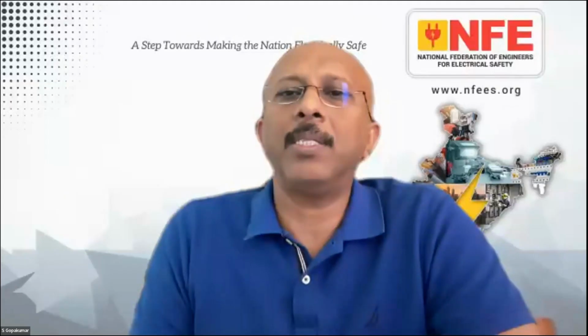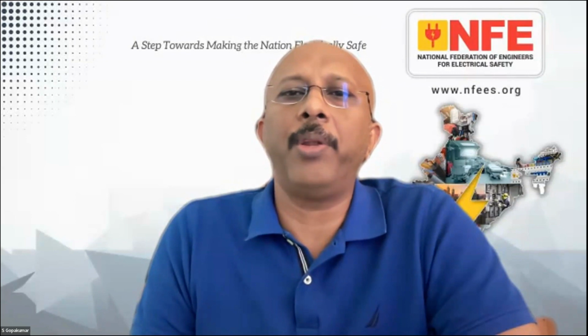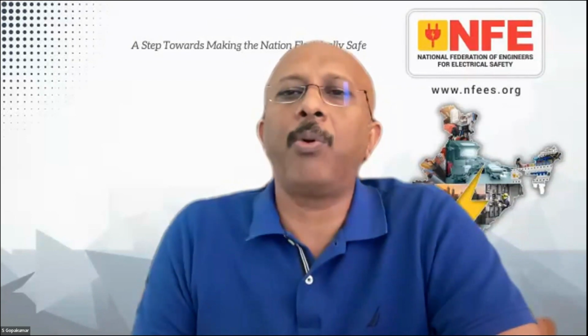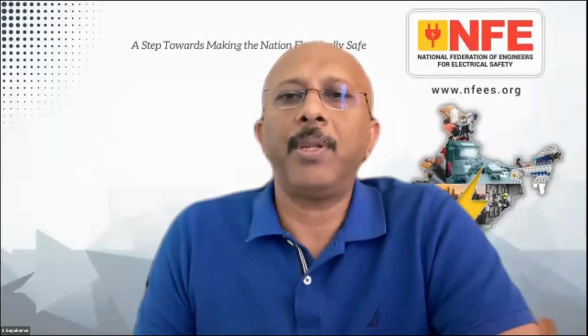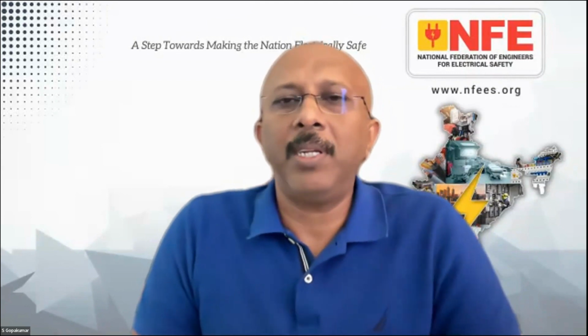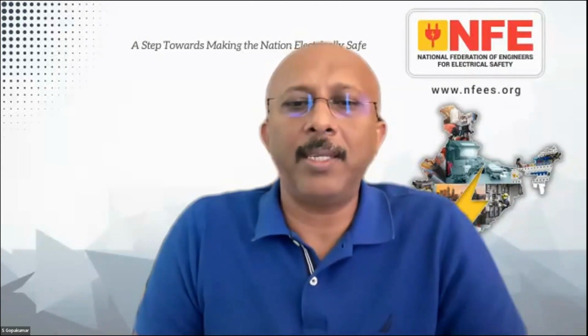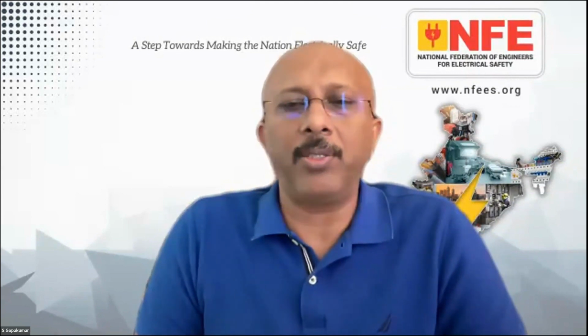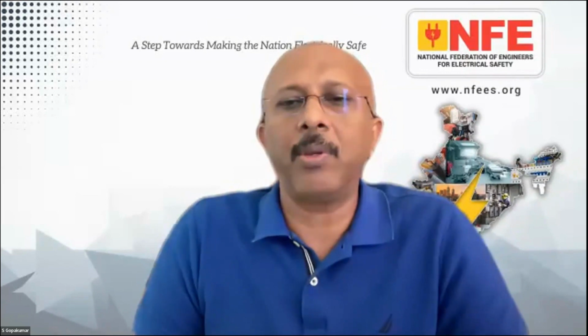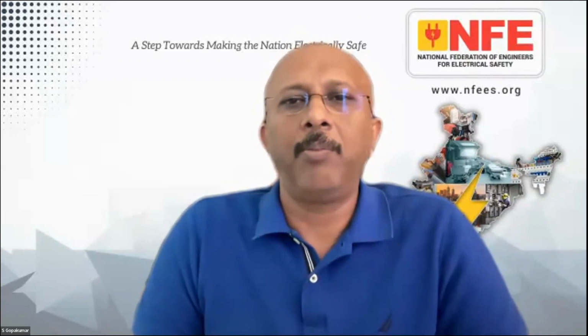So now, Mr. Ramakrishna asks: what are the suggested remedial measures or checks to reduce earth fault loop impedance if found to be high during measurement? So, Mr. Ramakrishna, as I said, in most of the cases in the Indian context, the values are quite high because in a lot of cases our protective devices are overrated.